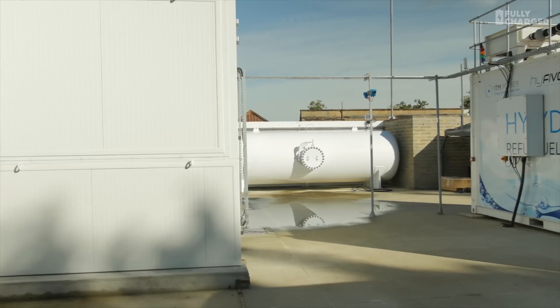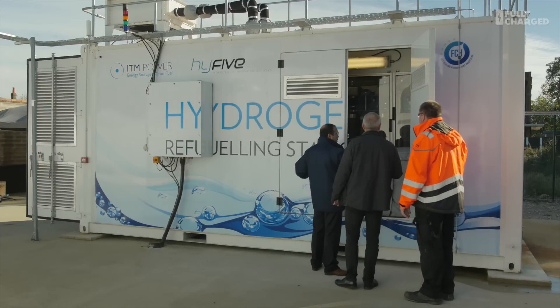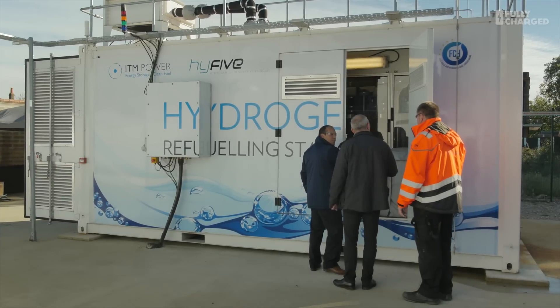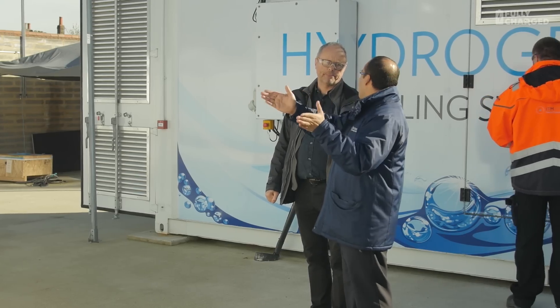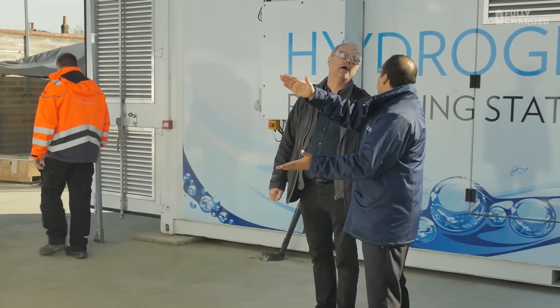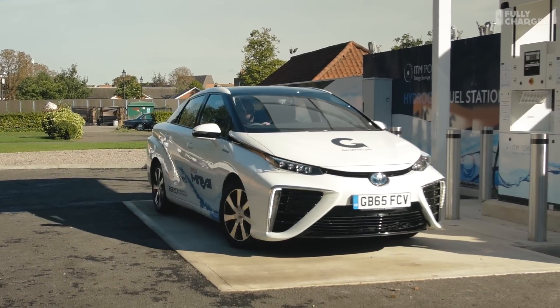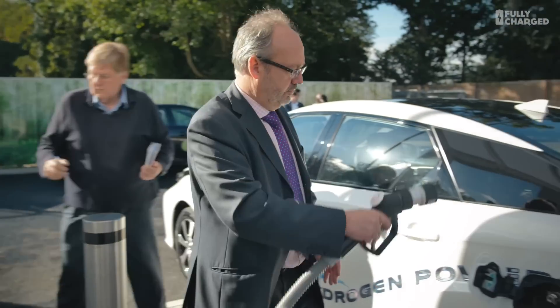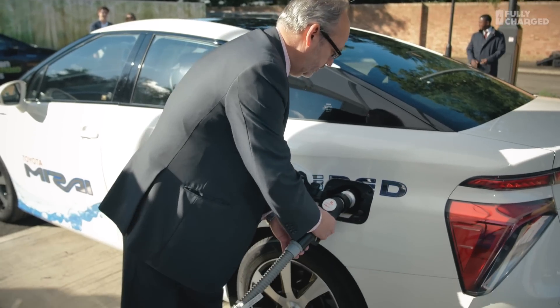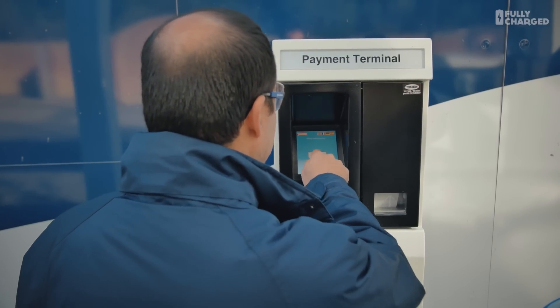Within this container we have the electrolyzer stacks, and then we have all the utility — this is a water purifier, for example. We have a gas compressor that takes the gas from 20 bar up to 1,000 bar. Within that compressor, at the lower level, we have high-pressure stores. We're storing hydrogen at 1,000 bar, and then that gas is available on demand every time a vehicle comes.